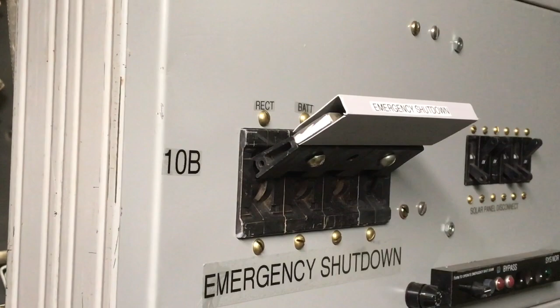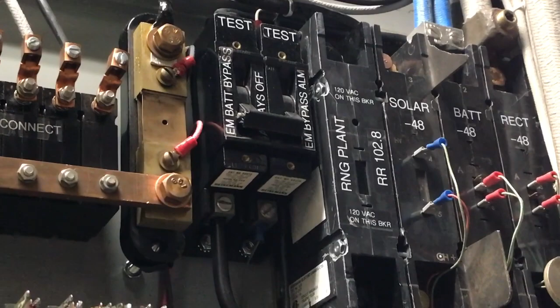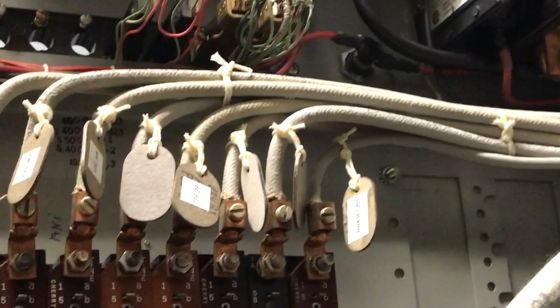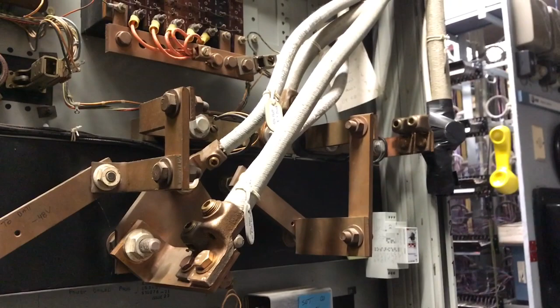This is mounted in my Stromberg XY power distribution board, and this would not typically be in a setup like this in a real central office. In a normal real central office, there's no provision to turn the entire office off at any one time. Maybe a little tiny baby office you could do that, but larger offices do not have a master disconnect. Here's the rear of the master disconnect, and also circuit breakers for the XY to the different frames in the XY switching system. And then this is the big bus for the entire office. Those are live 48 volts from the battery, the rectifier.